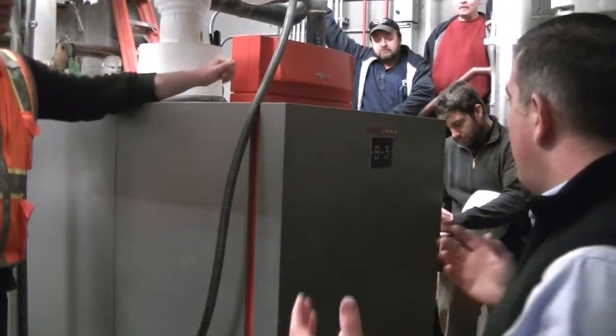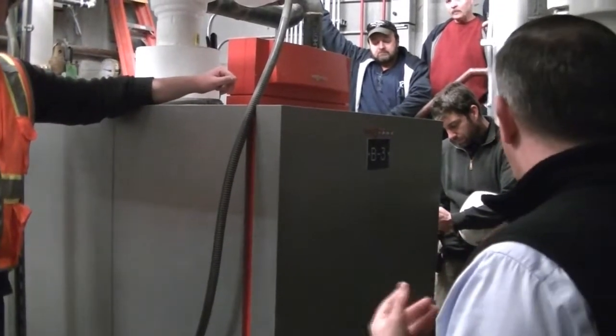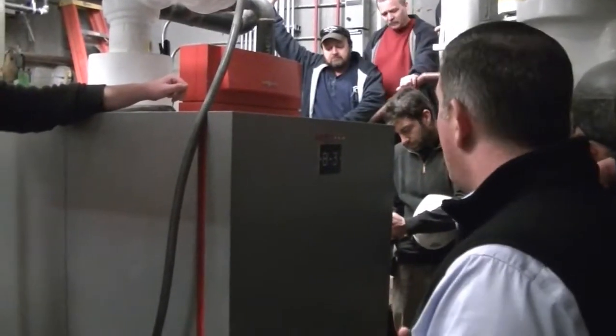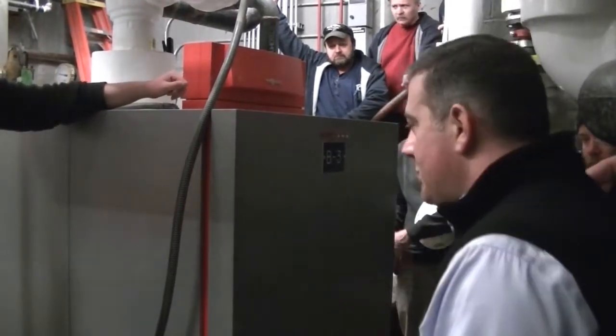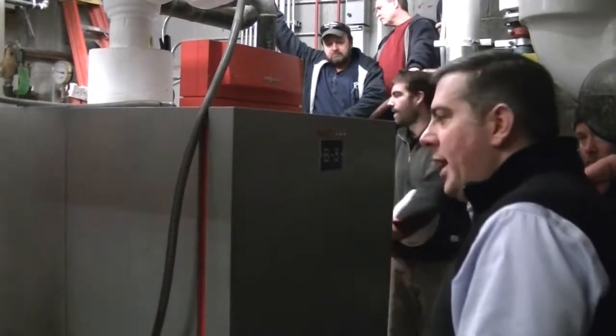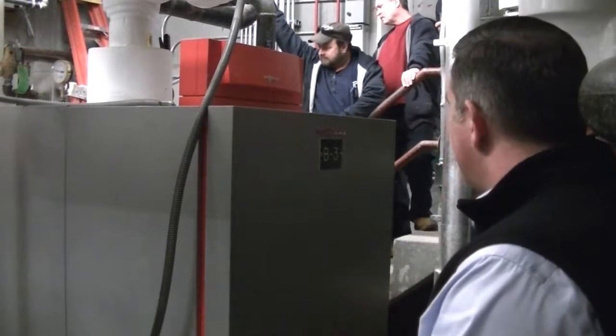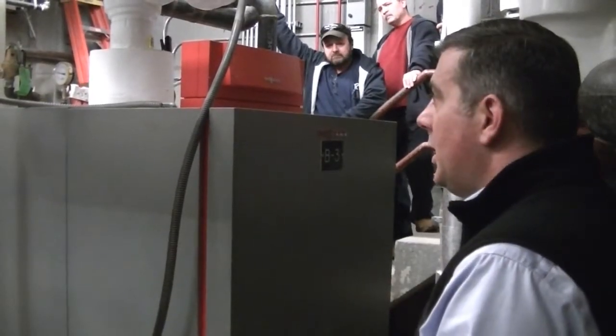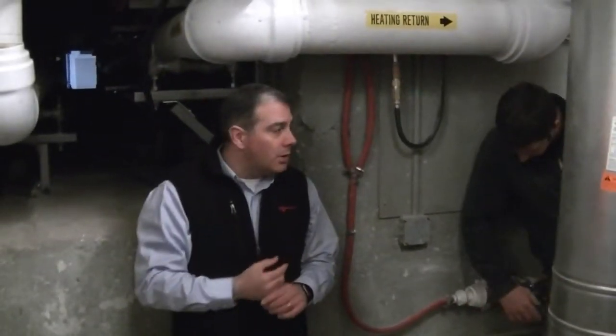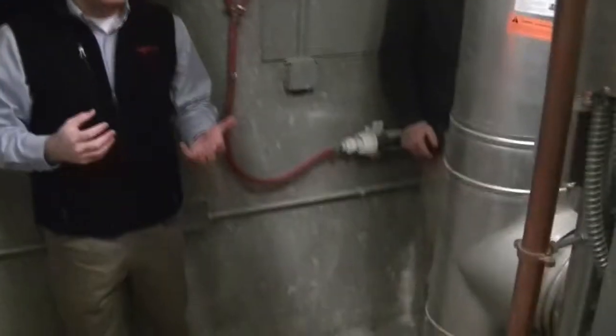The other thing you want to keep in mind about condensing boilers is you've got one other thing that's different than you'd have on a normal boiler, and that's around back. We can't all probably file in around back, but you'll see on the back of the boilers, there's a little black box with a hose connected. The back of each boiler, the boiler upstairs has one as well, and that's a condensate neutralizer. So when we've cooled that steam back into a liquid, we get water, right? That comes down the flue gas, that comes down the chimney, and also comes out the boiler because we've condensed that water vapor back into a liquid.